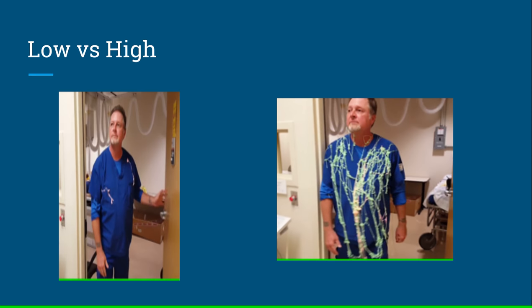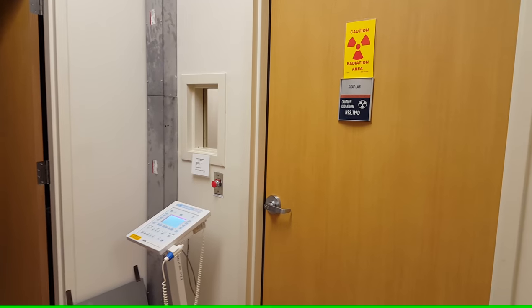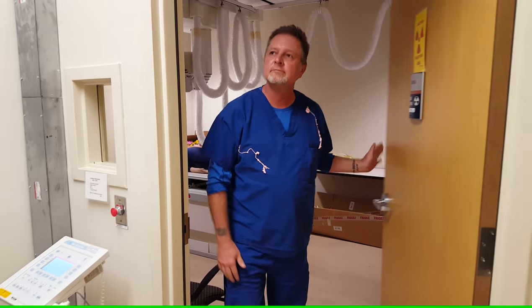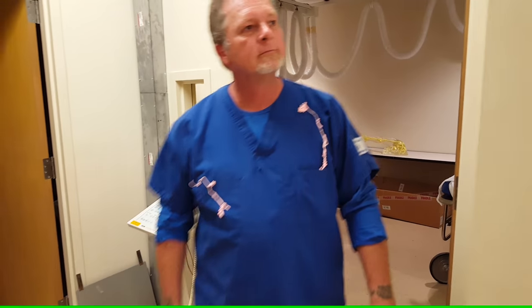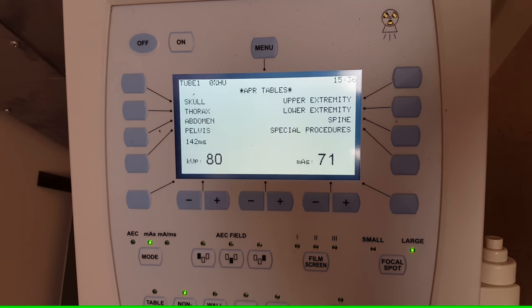This video demonstration provides a visual understanding of the amount of scatter produced when low KVP is used compared to when high KVP is used. When KVP is set at 60, the patient dose will be relatively low. As the patient walks out of the exam, the amount of scatter can be seen on his shirt. When KVP is increased to 80, the amount of scatter will also increase. As the patient walks out of this exam, it is apparent that the amount of scatter hitting the patient has increased.